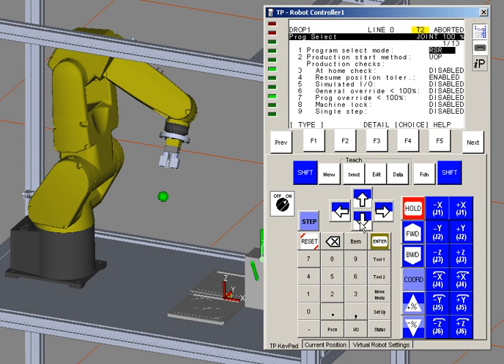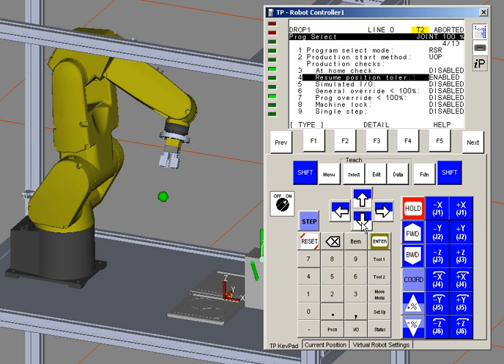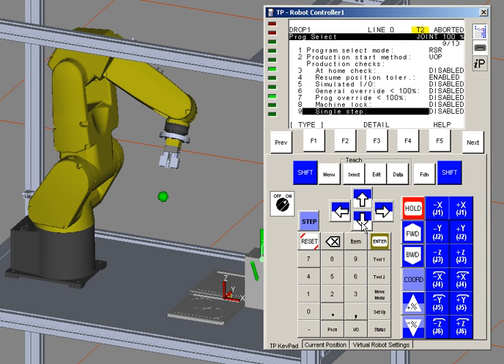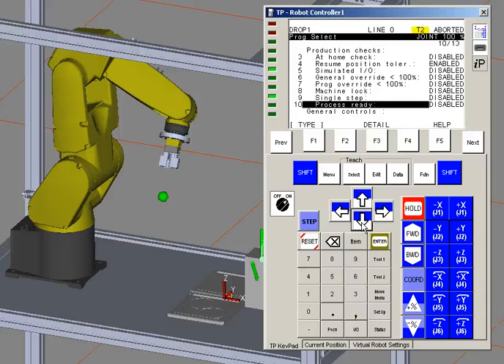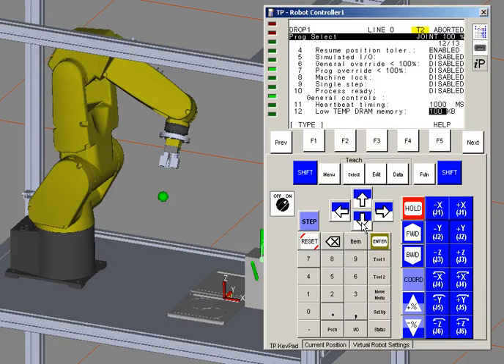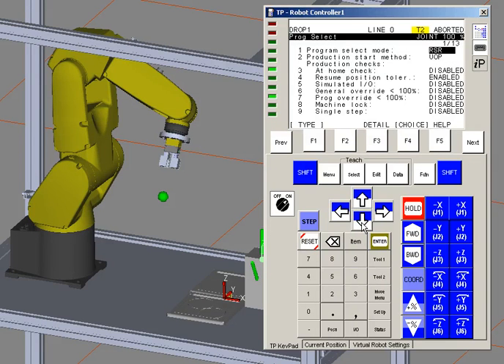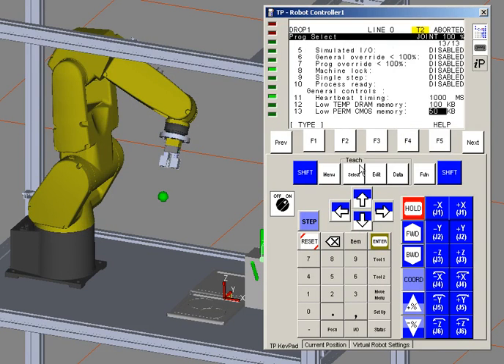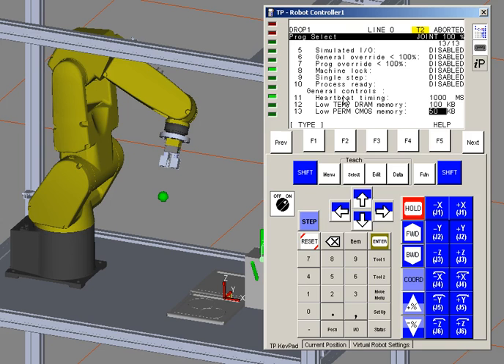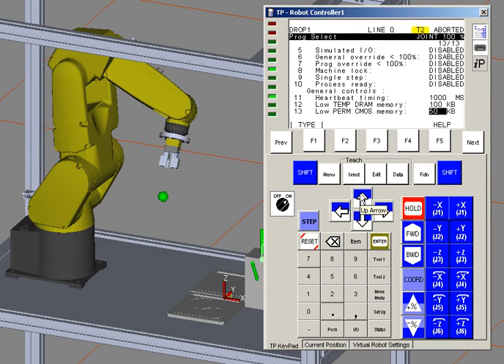So you have the option to force an operator to always crank up to 100%. You can also disable single step mode. The system operates differently when you run it in single step versus continuous mode in testing. There are also some other items here that can be set to define if low memory settings occur, and just to keep a general check on the system that it's still communicating and responding to other systems.